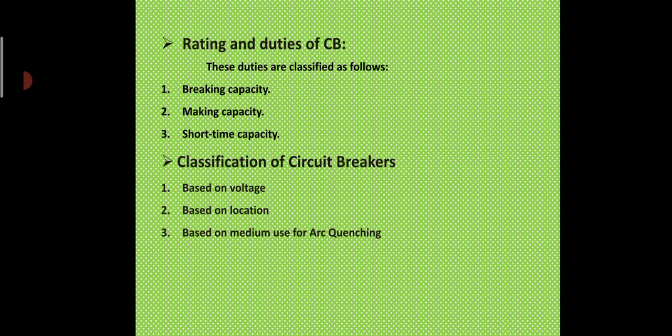It is not logical to express the breaking capacity in MVA as it is obtained by multiplications of the short circuit current and the rated voltage. While at short circuit, the voltage across the contact is much lower than the service voltage.